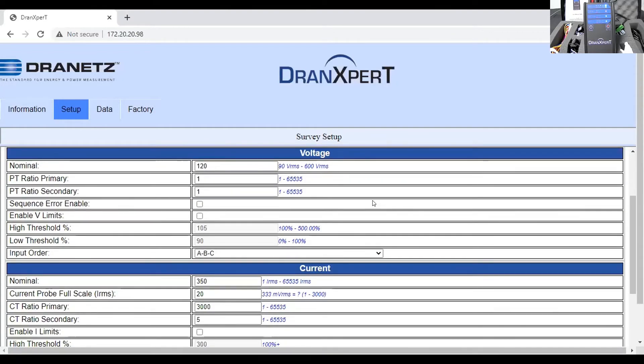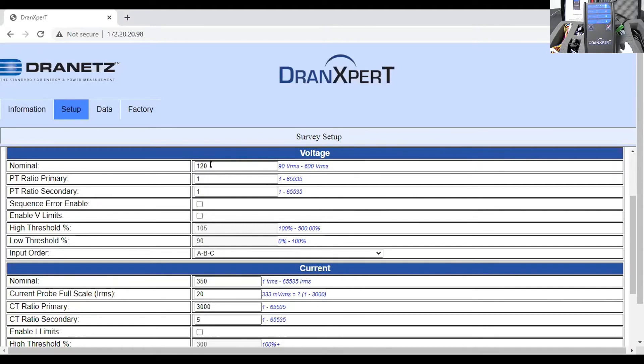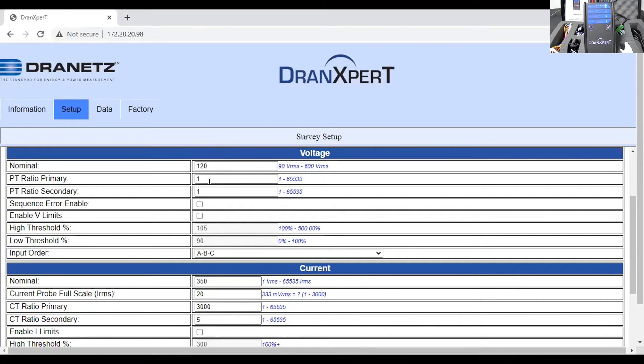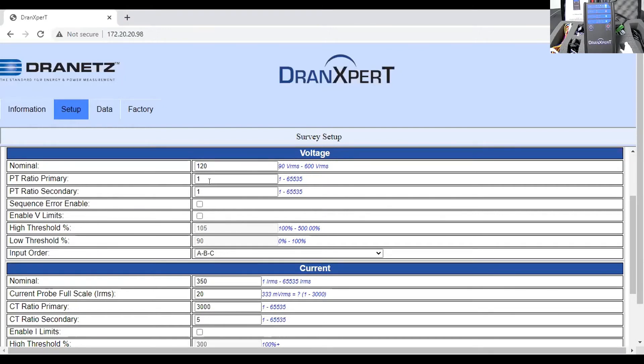As far as the triggers, you would start with a nominal. Okay, that nominal can be 120, can be 277, whatever the application calls for. You can see the range from 90 volts to 600 volts. PT ratios. Again, you know, this instrument typically is used in what we call low-voltage applications, which is up to 600 volts. But if you have medium and high-voltage applications, you can use this as well. But obviously, you're not going to connect medium and high-voltages direct to the instrument. You're going to go through PTs or voltage dividers. These devices have scale factors, if you will, or ratios. And that's where you would enter the values here.